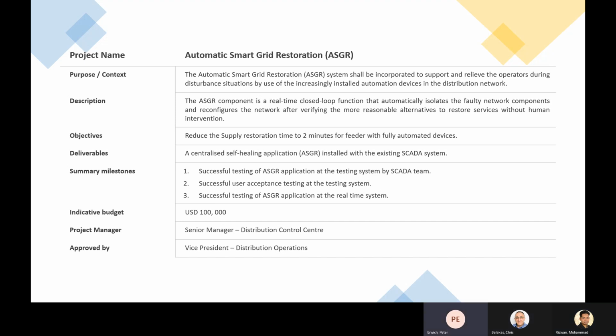Mohammed, I thought that DMS was doing that. Yes, we have a DMS for that one, but for the DMS system, it is just a supporting function for the control room operator, but this function will work as independent. The DMS system has a limited capability because if there are more than 2 or 4 or 5 disturbances, it can only advise the operator. The operator will be busy analyzing some outages, but meanwhile, if another outage comes, he cannot do it. Okay. Whereas automatic smart grid restoration, this application is independent. It can handle up to 100 outages at the same time. Oh, wow.